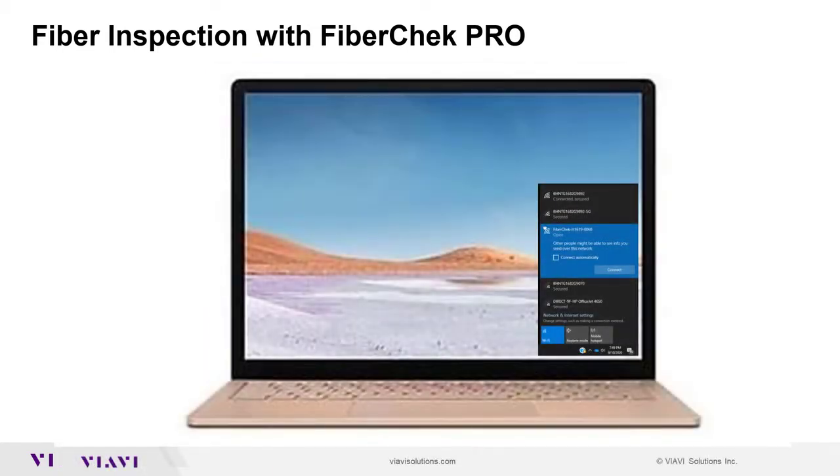The first thing you need to do is go into your Wi-Fi settings and select the FiberChek probe that's there. It will act as an AP, so select it and connect to it. Now your PC is connected to the FiberChek probe.